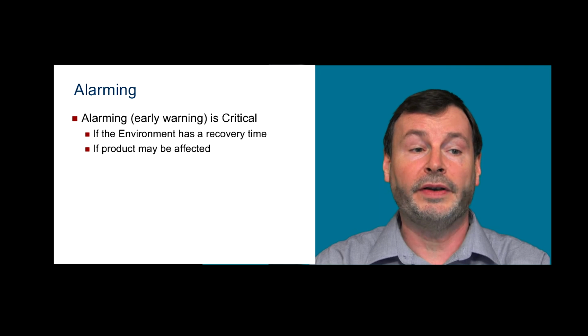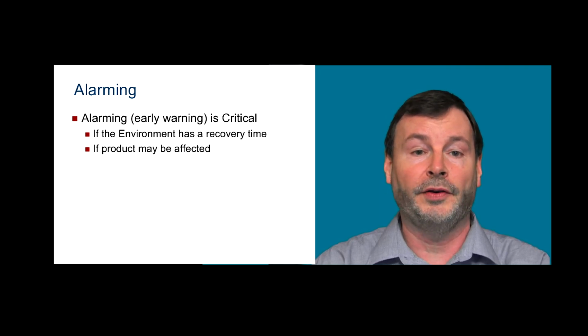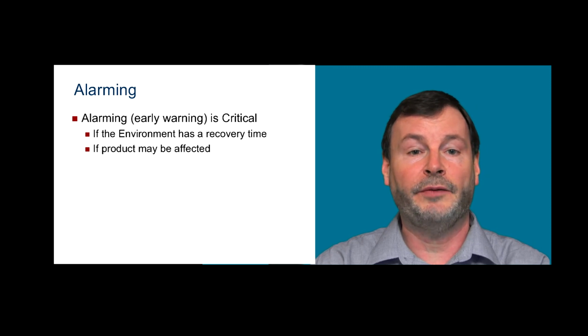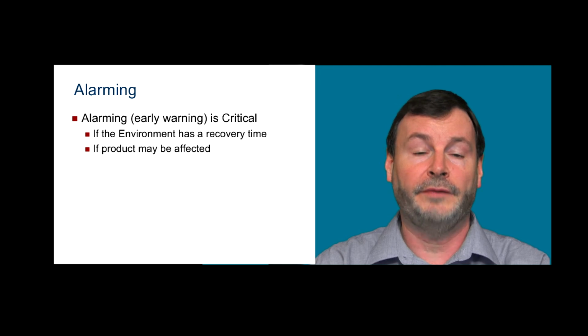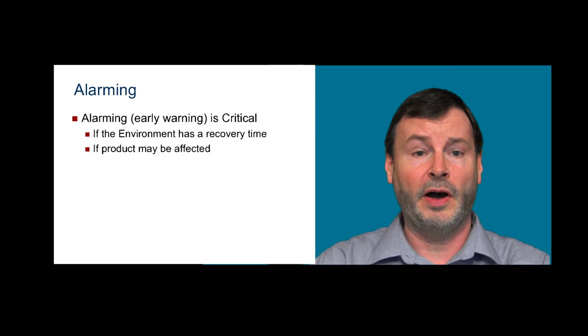It's also important to have alarming if a product may be affected somehow, either high humidity, which can damage certain materials, or even low humidity can cause certain material degradation. So again, if you have a material or process that can be affected by varying levels of humidity, it's important to have an alarming system that will both monitor and respond in a timely manner.